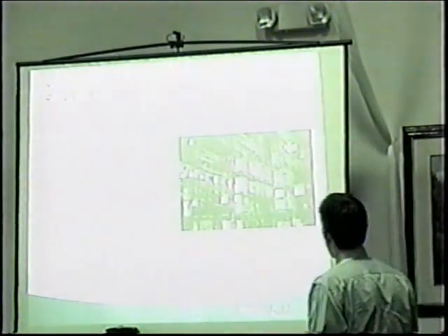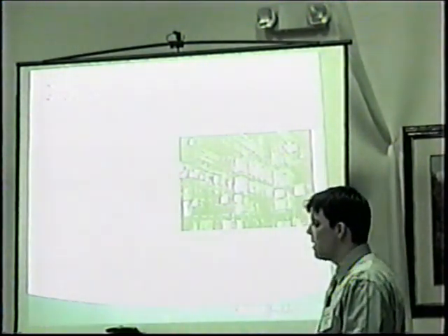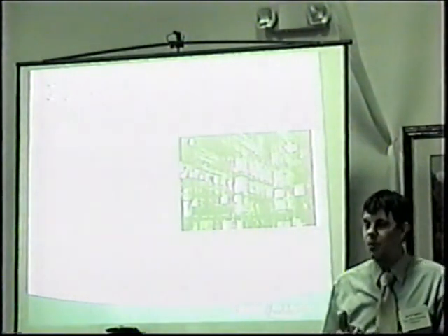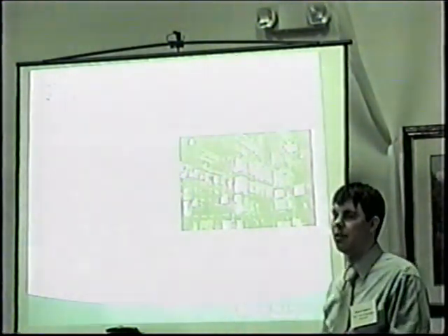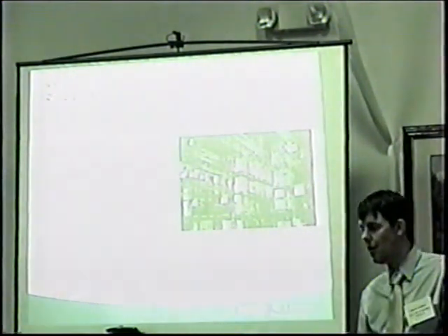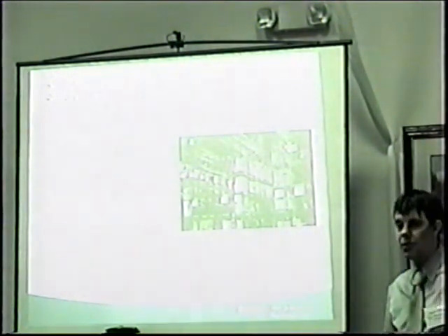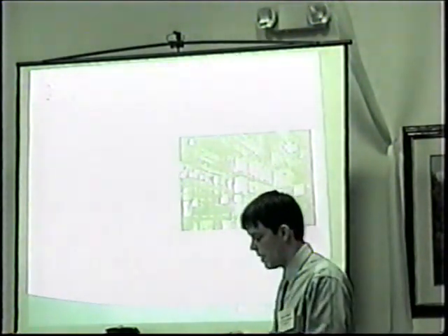So a couple of quick rules of thumb. The higher the storage, the more challenging the fire. We know that. Increased clearance delays sprinkler operation times, resulting in larger fires at the time of operation. There are actually cases where tests have been run with higher clearance but lower commodity height, so if you had 30 feet of storage with a 45-foot ceiling as compared to 40 feet of storage with a 45-foot ceiling, the lower storage height proves to be a bit more challenging, which is problematic because no one keeps their warehouses full. And I think that's actually one of those things we haven't addressed very well as an industry.